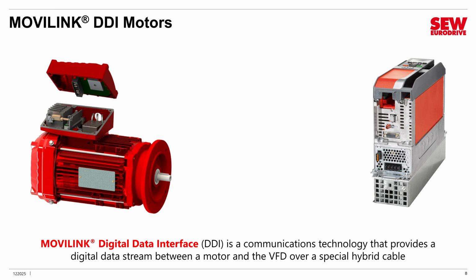Now I want to talk about a related topic, something called MOVILINK DDI motors. MOVILINK DDI, which stands for Digital Data Interface, is a communications technology that provides a digital data stream between a motor and the VFD over a special hybrid cable. MOVILINK DDI was introduced around the same time as the MOVI-C portfolio. It's a feature that's available in many SEW Eurodrive motors of different kinds, for example, asynchronous motors and servo motors. Its purpose is to create a single cable solution between an SEW motor and an SEW VFD.